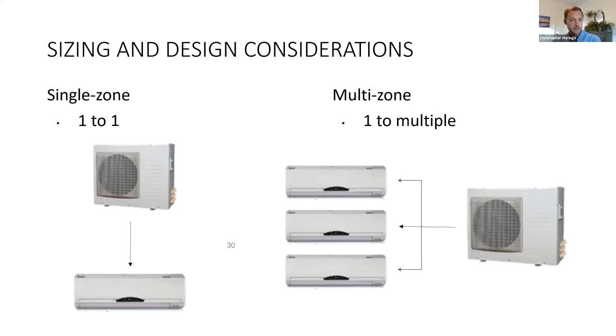There are pros and cons to single zone versus multi-zone units. Single zone, or 1-to-1, units are incredibly efficient at both heating and cooling. The outdoor condenser can connect to a ductless or ducted unit, depending on its size and the indoor unit type, conditioning anything from a small room to a whole floor. Single zone units offer excellent control, comfort, and the highest efficiency.